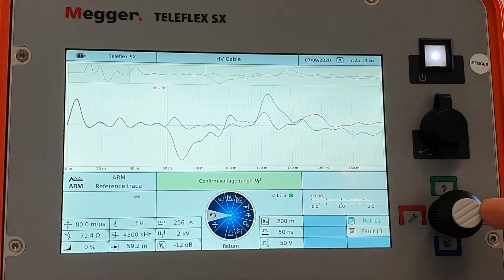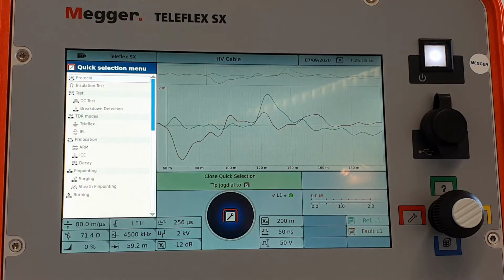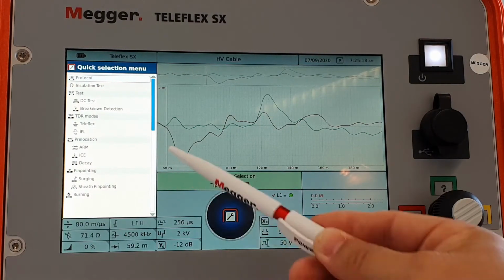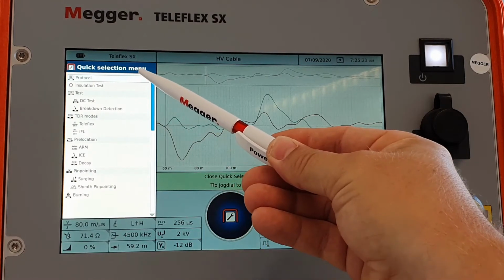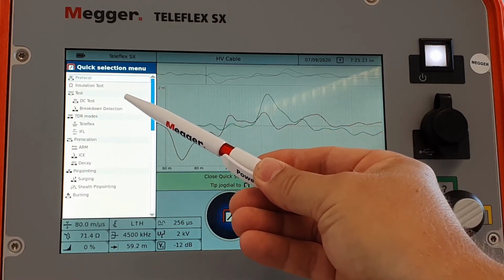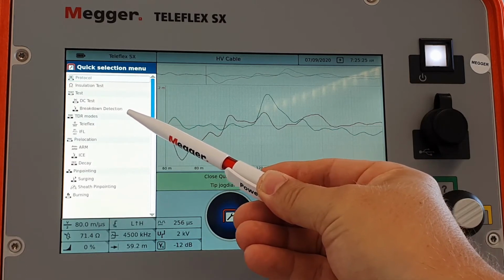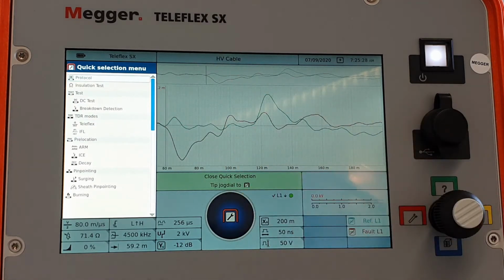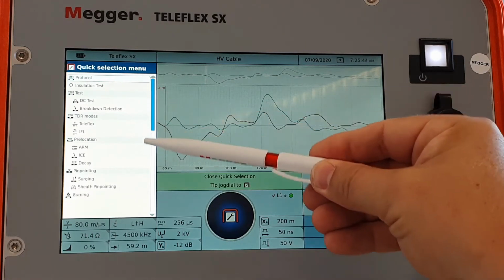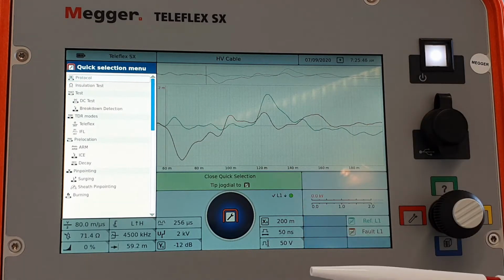The most important one, clicking to the left, is our menu for the modes. We have a protocol feature, insulation test, DC test, breakdown detection, which is practically the same as the DC test. But here it will save for us the value of the breakdown, and the voltage will not, after the breakdown, go down and continue. And this way we can easily read what was the breakdown voltage, which later we can use for the fault pinpointing.